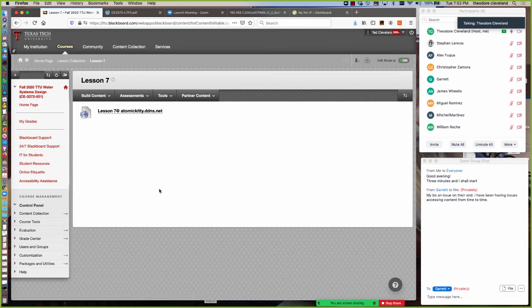What you'll do is the design guideline tells you the spacing fire hydrants have to have, plus some special stuff for cul-de-sacs. And so what you use that to find out is how many fire hydrants you need for that neighborhood. Let's say I don't know what the number is, let's say it's 18. And I believe the spacing in the San Marcos manual is 500 feet. And that's a pretty considerable distance, so it's pretty unlikely that a fire department could put more than 2 hydrants in service at any one fire. They don't carry that much hose.